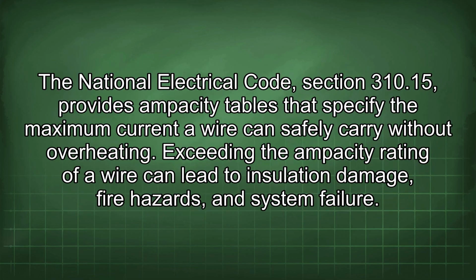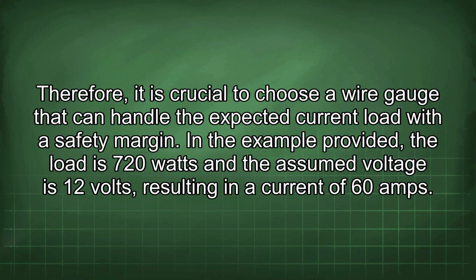The National Electrical Code, Section 310.15, provides ampacity tables that specify the maximum current a wire can safely carry without overheating. Exceeding the ampacity rating of a wire can lead to insulation damage, fire hazards, and system failure. Therefore, it is crucial to choose a wire gauge that can handle the expected current load with a safety margin.